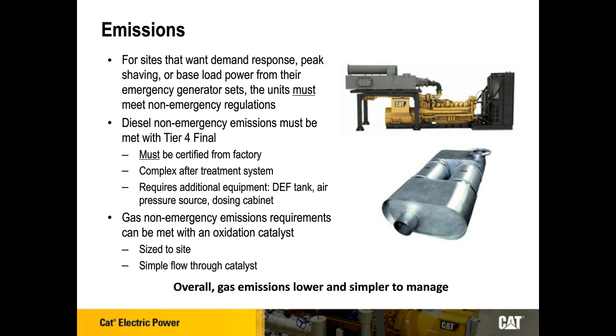So what type of requirements are needed for both diesel and gas generators? Starting with diesel, non-emergency emissions must be met with Tier 4 final. All product coming and shipping out should be Tier 4 final, and it must be certified from the factory as a Tier 4 final product, which, as you can see in the top right picture, involves a complex after-treatment system. Most of the in-cylinder work has been completed to get as much reduction in emissions as possible, and now a lot of the work needs to be done on just the exhaust coming out of the machine. It's a very complex system that reduces the emission levels.